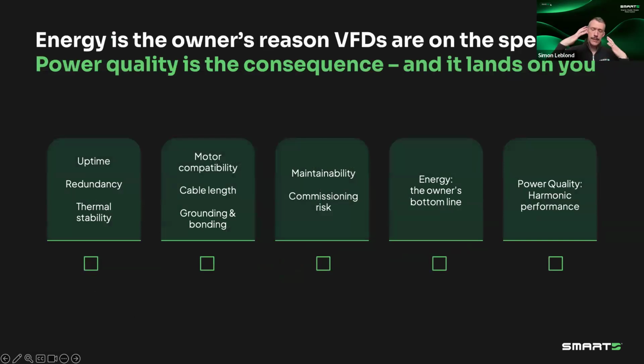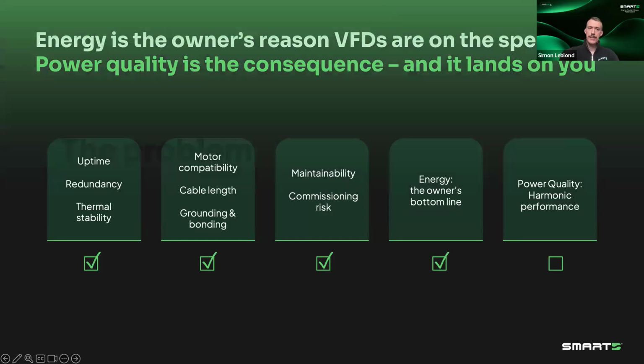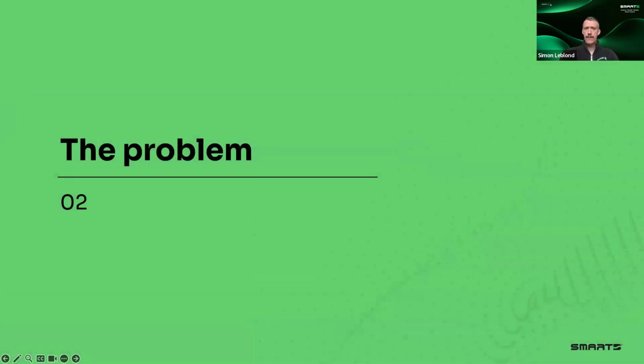Now, if we look at your list of priorities in a data center, obviously the first one is uptime and redundancy. Then you need to make sure that your motor control is laid out properly. You need to make sure that everything's maintainable and that your commissioning goes smoothly. But, and this is really the underlying challenge, the energy bill is the owner's bottom line. So you need to put in those VFDs. And as I showed just before, those now make power quality and harmonic performance your problem and something you need to consider.